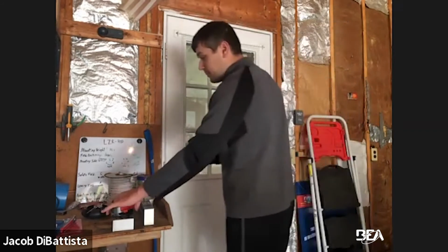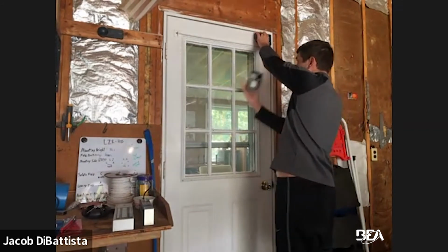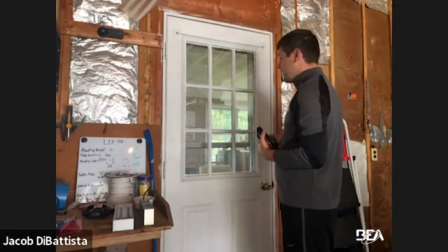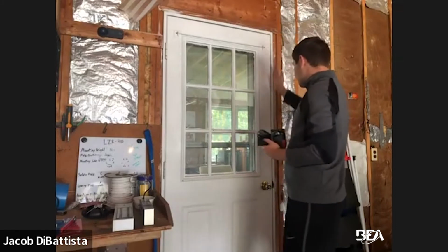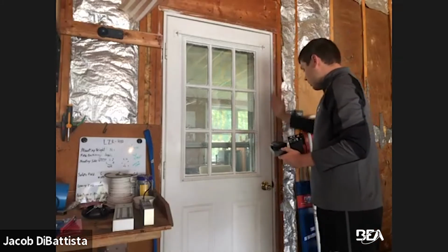The regular FLATSCAN, let's just say it was up here. It's just one single curtain along this doorway. So whenever you're doing a teach-in, you're going to swipe your hand on the leading edge of this door and tell it, I want the field to cut off here. And it's going to go all the way down to the ground.